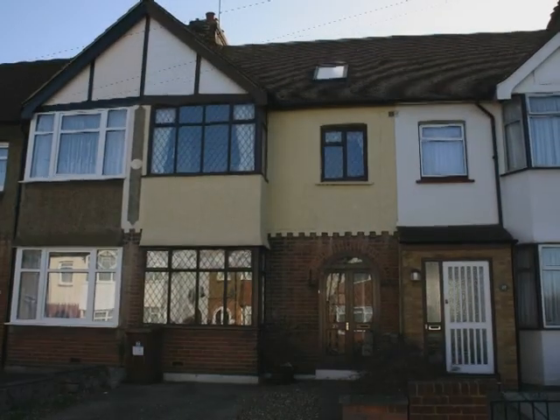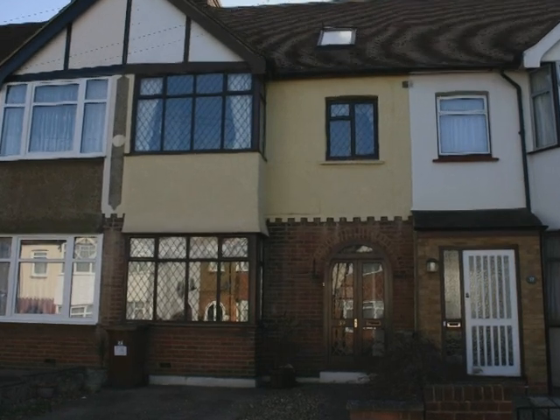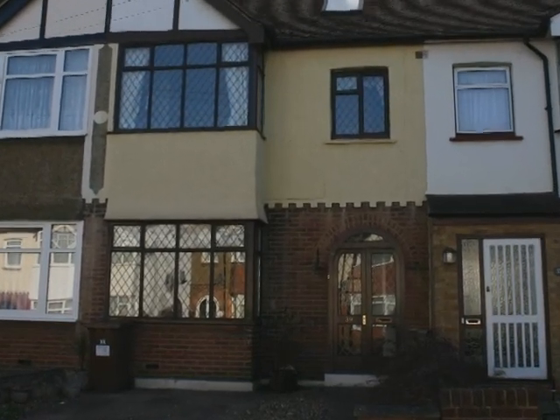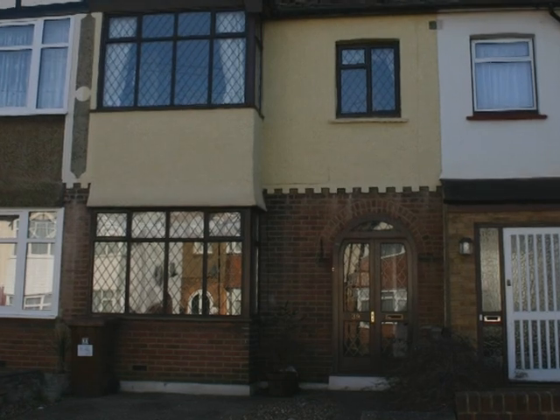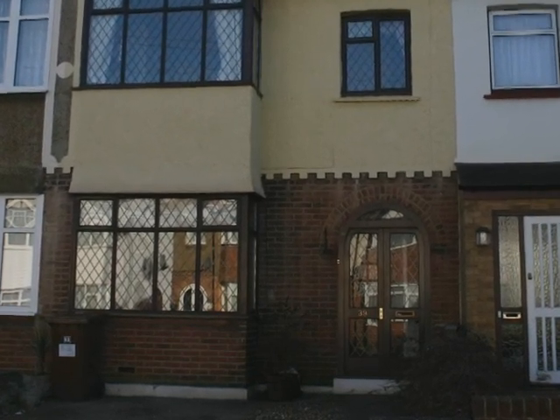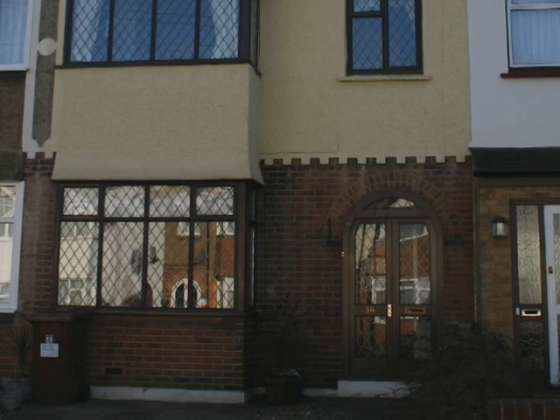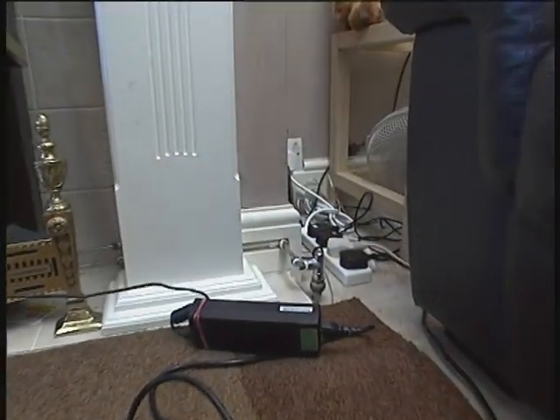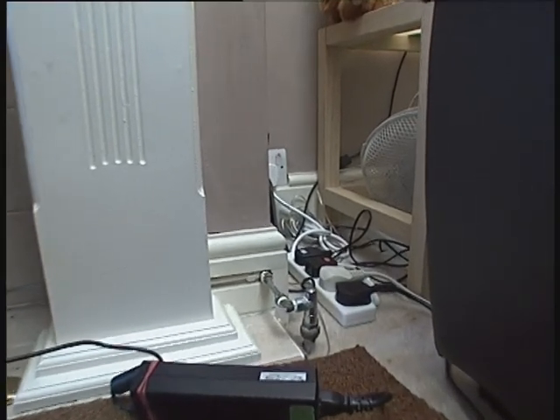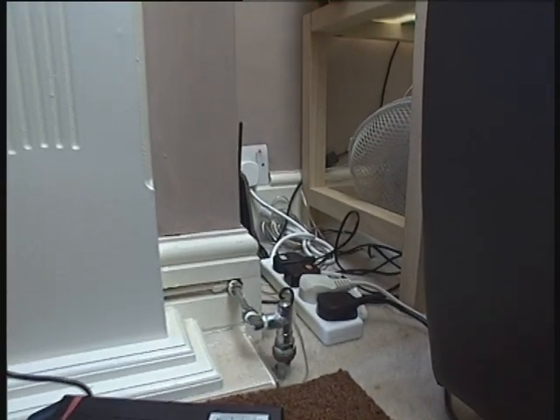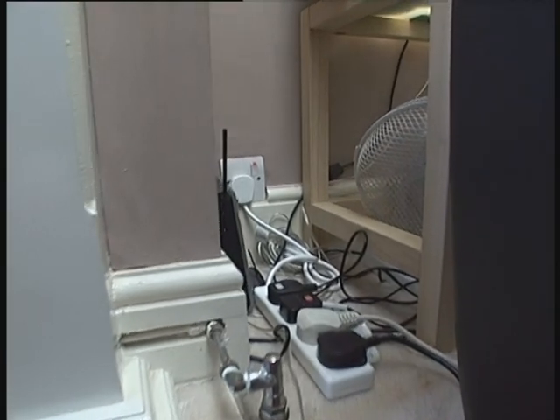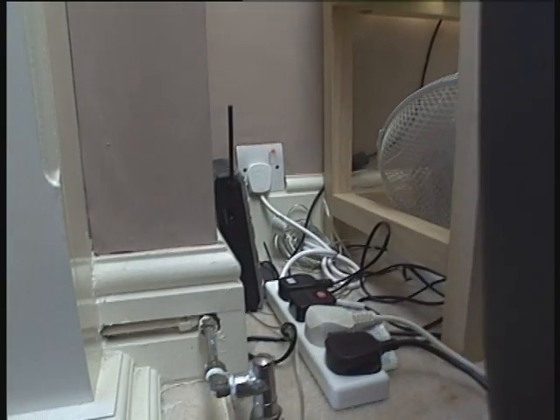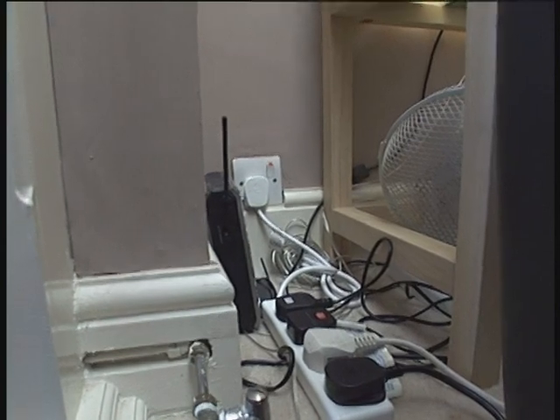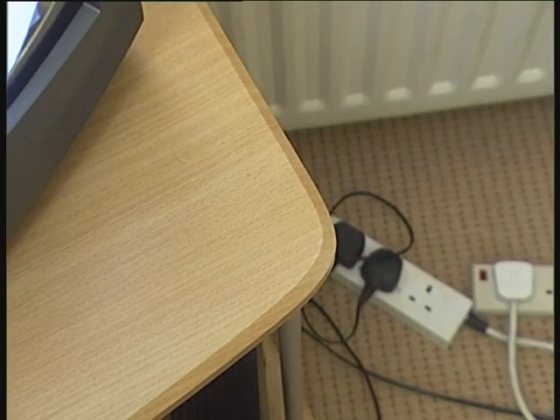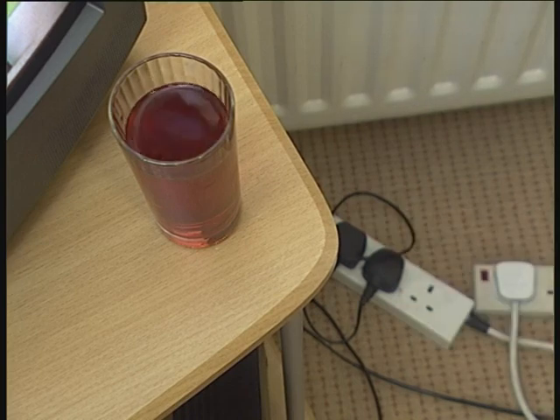This house's electrical installation is very typical of one installed in the 1950s, and unfortunately, the design of its electrical installation never anticipated the wealth of electrical items we use to achieve today's standard of living. So sights like this are very common. Extension leads and adapters to provide extra power points are an area of high risk. They not only have the potential to overload the part of the circuit they're connected to, but are tripping hazards, and could even invite potential electric shock situations, such as this.